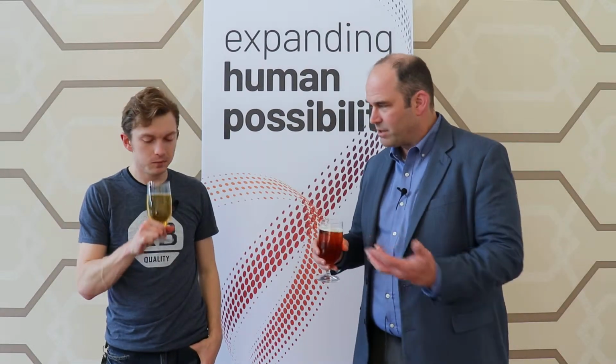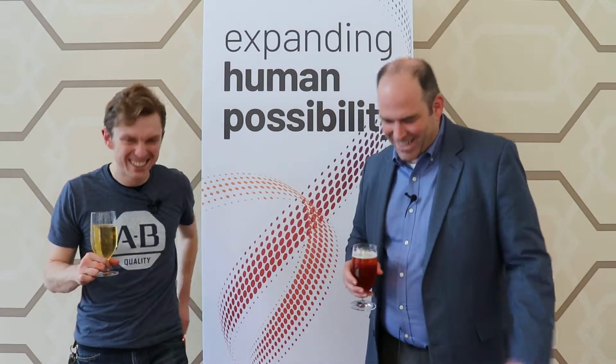Absolutely. One of our shared customers, a company called American Castings in Oklahoma, has been around 100 years, so they have tons of old equipment. They wanted to start upgrading their old Square D Symax system. They didn't want to do the rip and replace. They had 1,000 points of data that they would have to rewire. What they did was put in a new Logix controller. They used Prosoft migration products to talk directly to that old Square D I/O.